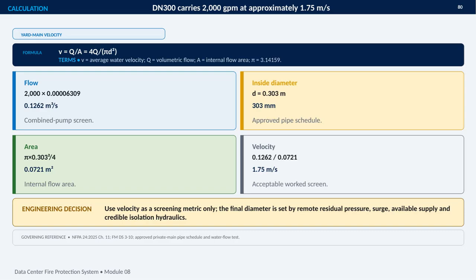This slide works through a velocity check for the yard main. The example considers a DN 300 pipe carrying 2,000 gallons per minute, with an inside diameter of 0.303 meters. We begin by converting the flow to metric units. 2,000 gallons per minute becomes approximately 0.1262 cubic meters per second.